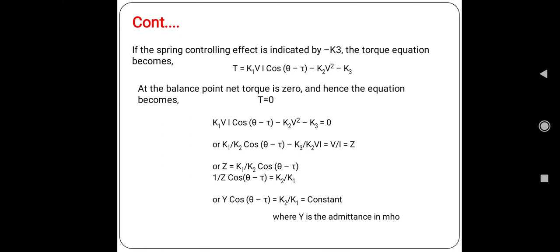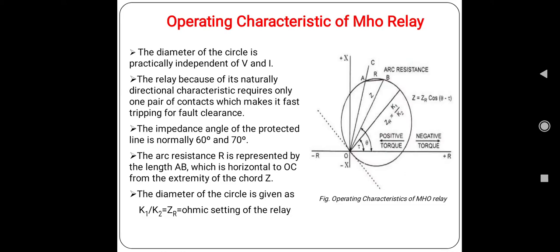Hence the relay has one circular characteristic, and we will see the characteristics here. The diameter of this circle is practically independent of voltage and current except at very low values of current or voltage when the control spring effect is considered. But due to consideration of control spring effect, the diameter will decrease.